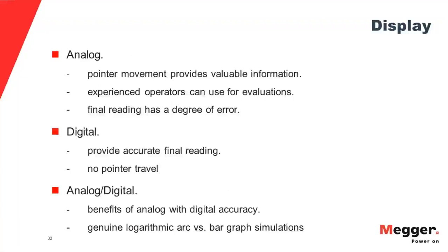And the displays. The old analogs are still around. A lot of people like them. Digital has become the new thing, and that's what is mainly on the market at this point. And there are good and bad sides to both of them. The analogs gave you pointer travel, and your experienced operators were very good at recognizing pointer travel. They wanted to see the pointer traveling up to higher readings, because typically on analog units, the pointer rests on the high end, and when you start the test, it pegs low, and then it drifts back up. And those experienced operators were looking for smooth pointer travel. And if they got that, hey, that was good.